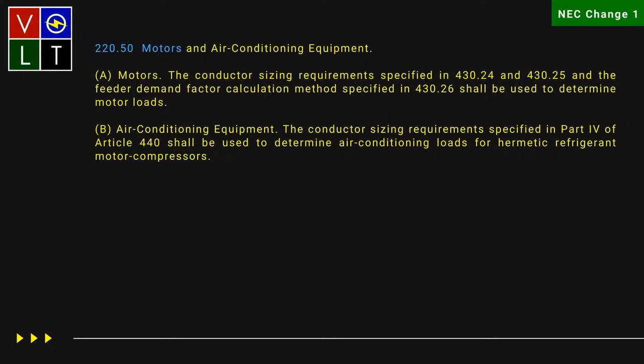The reason this is important is because it's going to do a full clarification when you're looking at the motors when you're doing this. So since they added this in 220.50, if that AC unit motor is larger than the other motor you're calculating for, like a commercial installation, then that AC unit would be the largest motor when you're doing 220.14C. So this came through code-making panel 2, right?